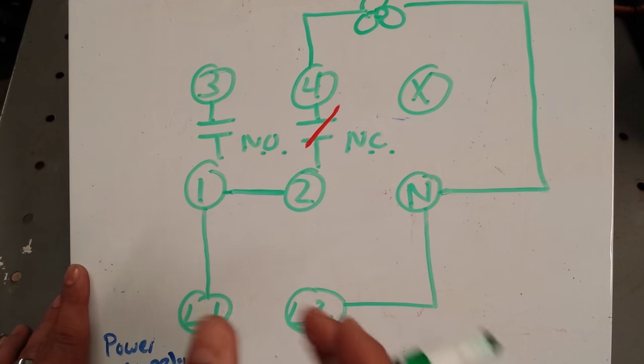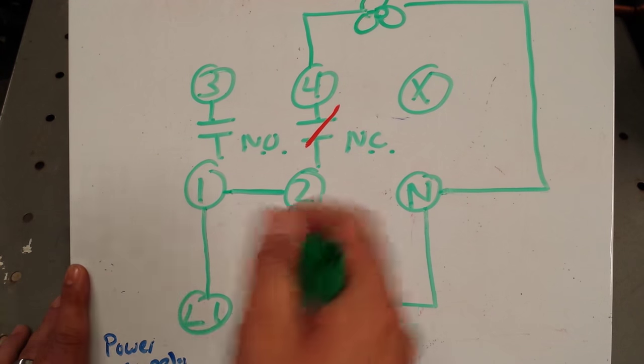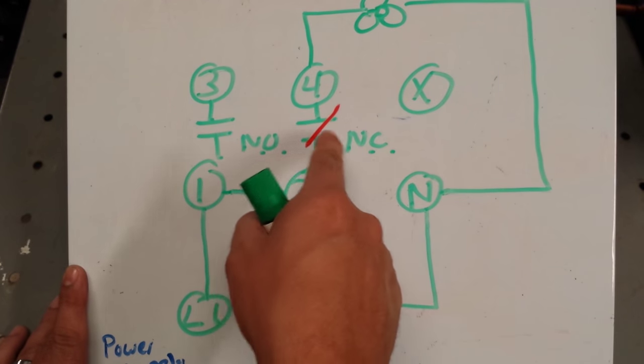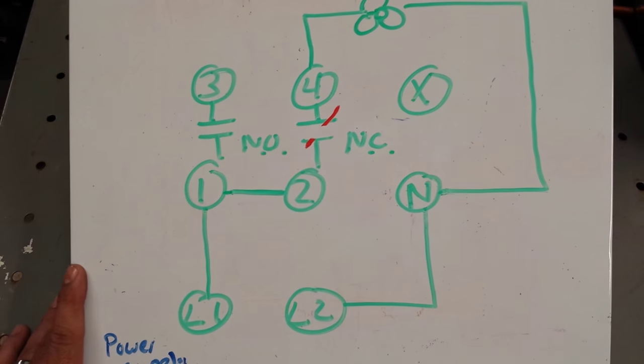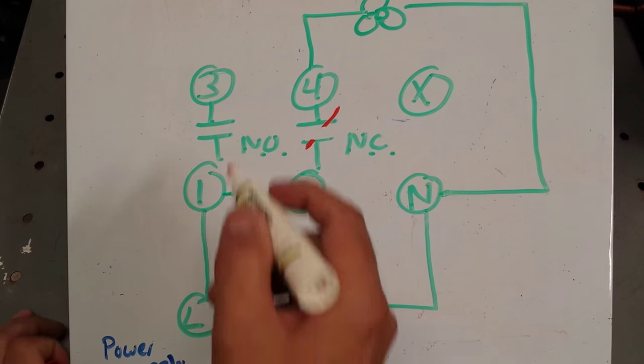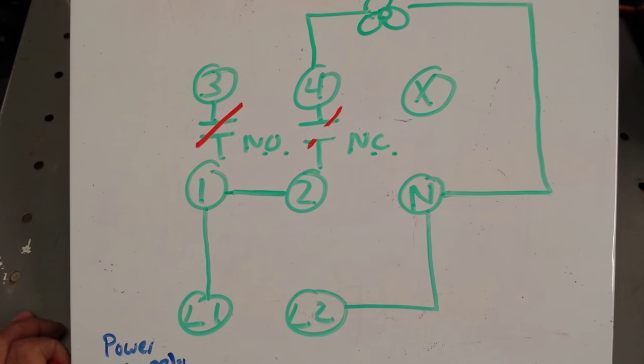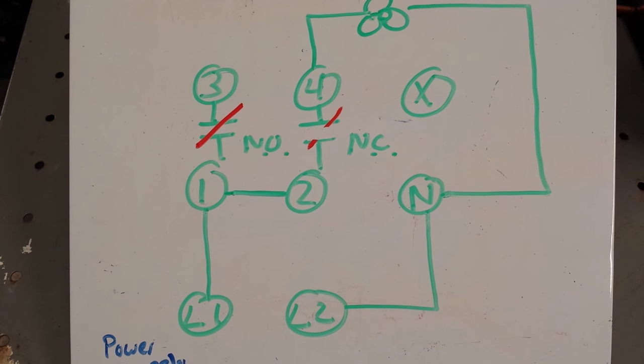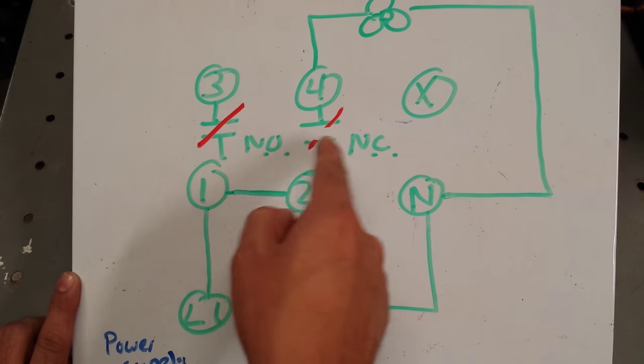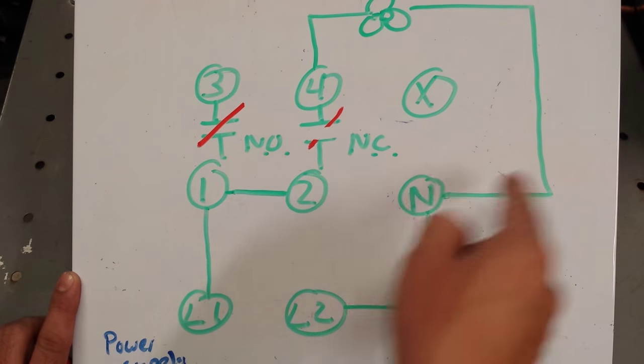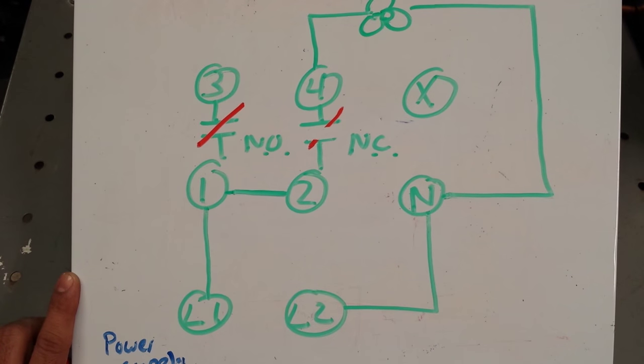The moment this defrost clock turns and gets energized by one of the pins, and defrost is initiated, our contact points between terminals 2 and 4 is going to open. And then 1 and 3 contacts will close. When that happens, our evaporator fan is no longer running because our circuit is open. We don't have a complete path anymore. The fan motor is non-operational.